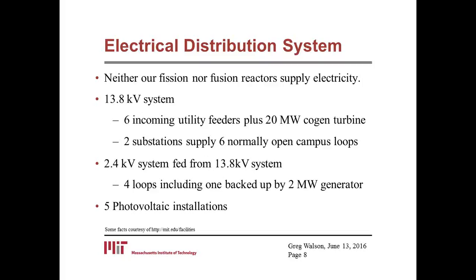We have two substations, essentially switch racks, that supply 6 normally open loops. Each loop starts at one of the stations, runs through with a normally open tie in the middle, and then back to the other station, so that we can backfeed a loop if we need to do work on a piece of it. That's fairly common.